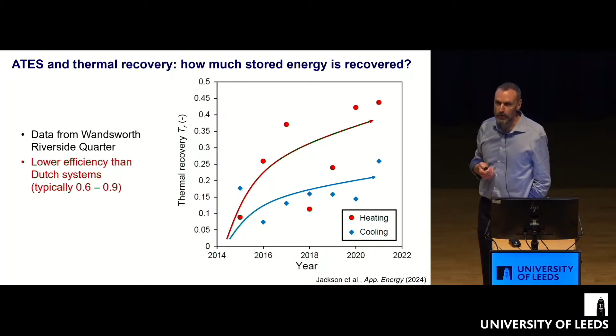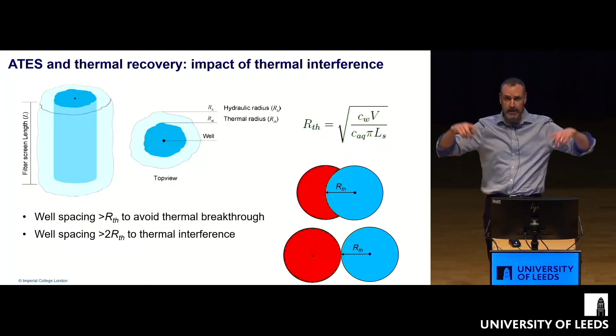When we inject warm and cool water into a nice homogeneous aquifer, as in my animation, you get these nice cylindrical plumes that grow and shrink. It's easy to characterize the maximum size of that plume, the maximum radius, in terms of what's called the thermal radius. One thing the Dutch would say is that you need to put your wells far enough apart to make sure you're not within that thermal radius. If you're too close, your heat will meet your cool well and your cool will meet your warm well. If you're a bit further apart but still too close, those plumes will interact with each other. If you put the wells far enough apart, you get nice separate plumes.